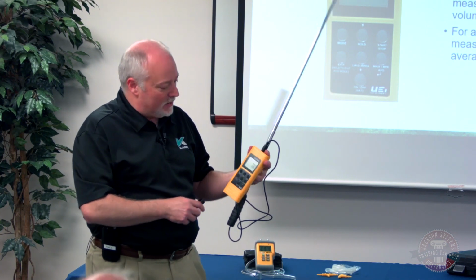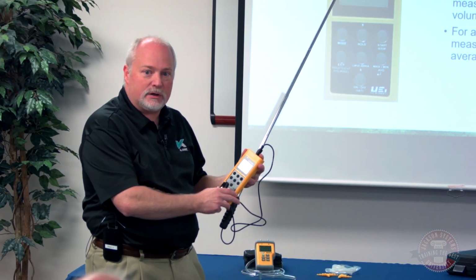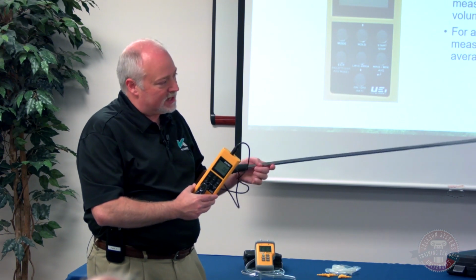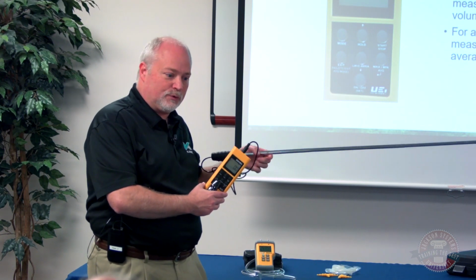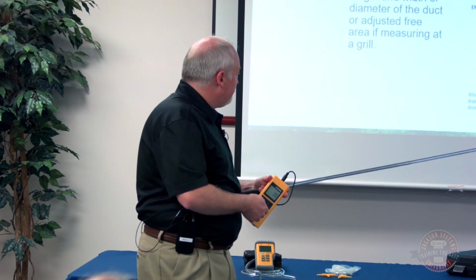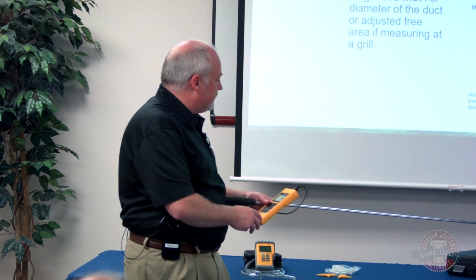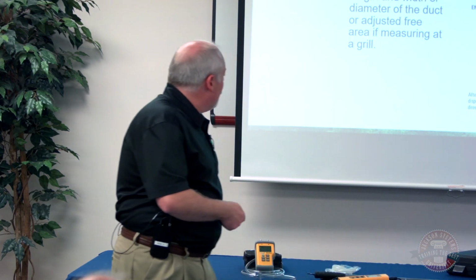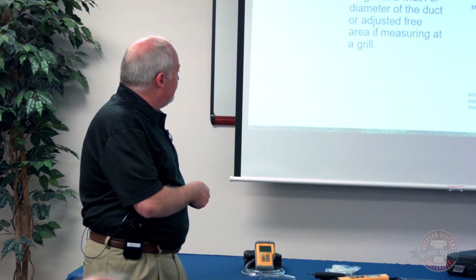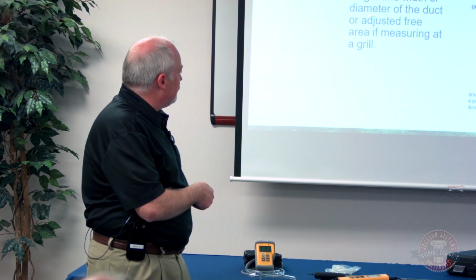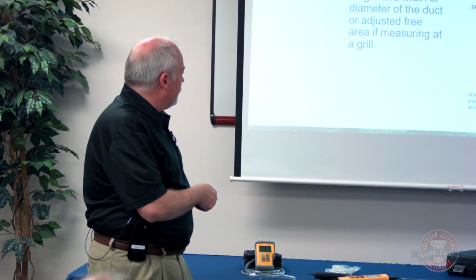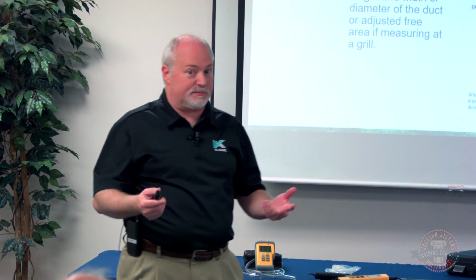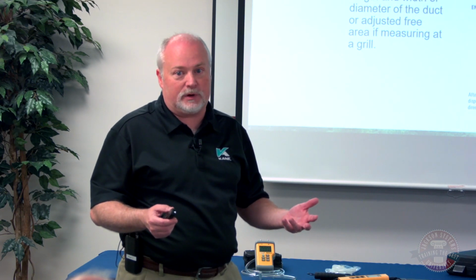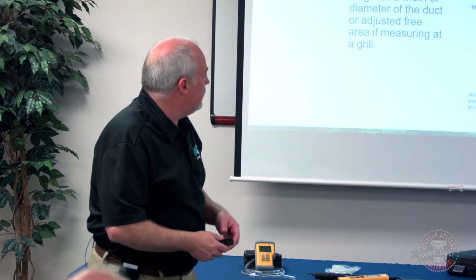Okay, so this allows us to do this because we've actually got a start and stop button on here that we can hit start for the timer to run, it'll take a reading, then we can hit stop. We can move over to our next opening and do that. Just real quick to walk through how we're going to do that. We enter the volume mode, then we're going to enter the length and width or the diameter if it's a round duct, and if we're looking at a grill, we're going to adjust that area for the free area space. Whether it's a 75%, which is pretty common open free area for a metal duct, or maybe a 40 or 50, if it's a wooden decorative duct, or rather grill.